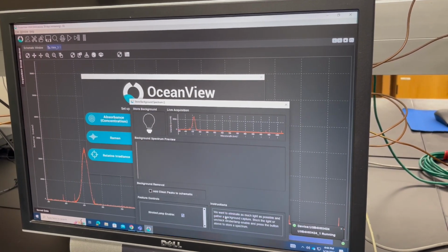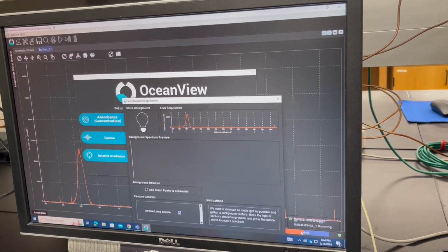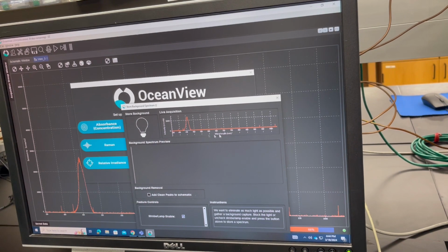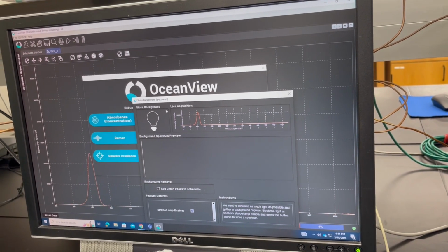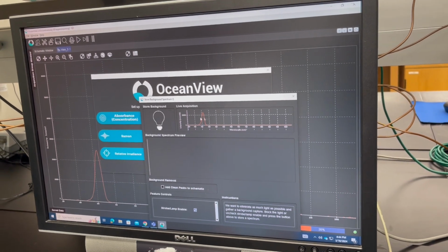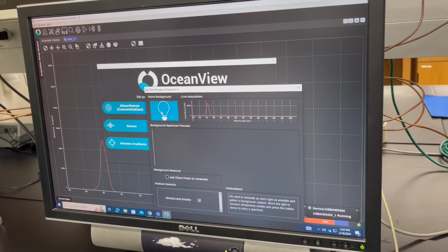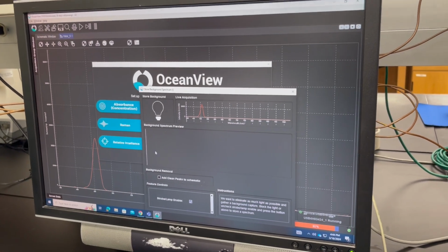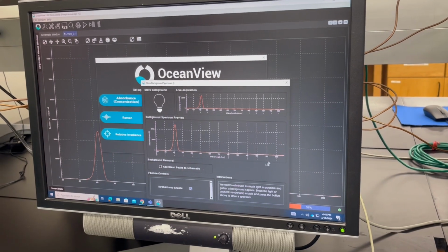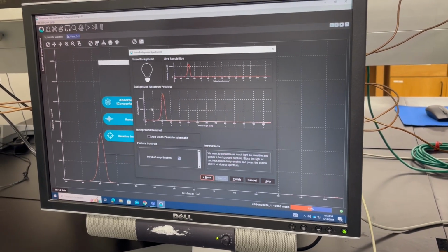We're then going to click on next, and once we have a run finish here, which when I click next, a run just finished, so we got a live acquisition to come up. I'm gonna go ahead and let this one finish as well. And then once you have a live acquisition, you're gonna go ahead and click on the light bulb, which is then going to take your next run and store it as the background that's going to be subtracted from each of your runs. And then once you have a background to subtract, you're gonna go ahead and click finish.